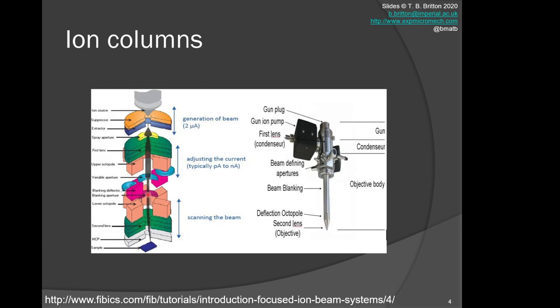Then we have another aperture, some blanking deflectors to blank the beam by moving it onto a lump of material to stop it going down the column, and then we have a series of lenses and deflection coils to move the beam across the surface of our sample. In practice, this is strapped on the side of a column—this is the physical reality, and this is what the cartoon or ray diagram looks like of that system.